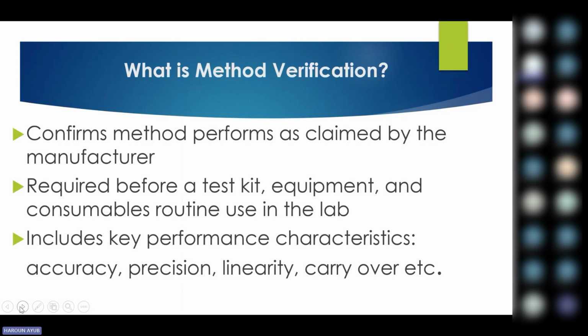So you'll find that if I've given you a linearity for, let's say, hematology, you'll find that for WBCs we have vial 1, so a total of 6 vials, but we have one vial that is level 1, another vial level 3, level 5, level 7, level 12, and level 13. While we are doing this particular test, you'll find that the manufacturer has advised you to follow the serial vials, so that in case you start off from level 13, there is that particular effect that might carry over to these other samples.